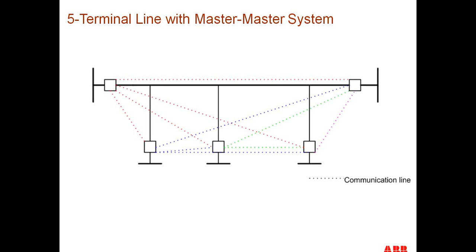The next is that there are two different ways that one relay can communicate with the other relays. One is called master-master, and in master-master communications, each of the relays receives all the information from each of the other relays. As you can see in this particular scheme, each relay is receiving all the information from each of the other relays. Each relay then makes its own decision about tripping, does its thing, and then tells the other ones that it has tripped. It's called master-master communications.